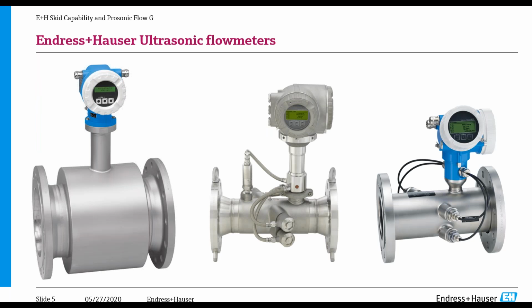Okay, thank you, Taylor. I'm going to start off right here. We have our ultrasonic inline portfolio. We actually have 3 meters serving inline measurement for ultrasonic. On the left is our original entry into inline measurement, our Prosonic Flow 92F. That's a liquid inline meter measuring liquids only. Then to the right, we have our Prosonic Flow B200. This was our first gas flow meter, inline ultrasonic, doing low pressure applications, really focused towards biogas applications. And then we have our new product, which is the main reason I'm here to talk about today. This is the Prosonic Flow G 300. This is the compact one. The remote version is the 500 version.